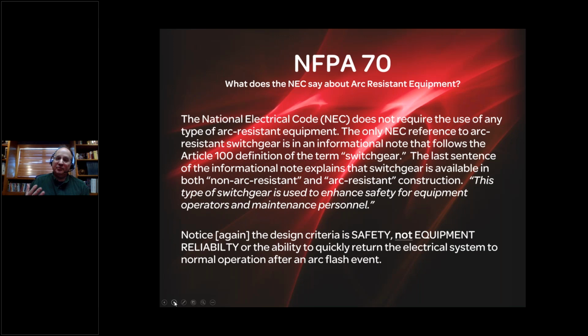And I should note, in one of the depositions that I have given, it was brought up by the defense side in an arc flash event that NFPA 70 does not require arc-resistant equipment. It doesn't. You can, but it doesn't. You have to remember when these things end up in litigation, you're not talking to engineers and technical professionals. And the point brought up by plaintiff's attorney is: so arc-resistant equipment is available, but you still chose non-arc-resistant. They said, that's right. He said, why did you do that? And he said, well, it's not required by the code. He said, it's not required, but why did you choose non-arc resistant?